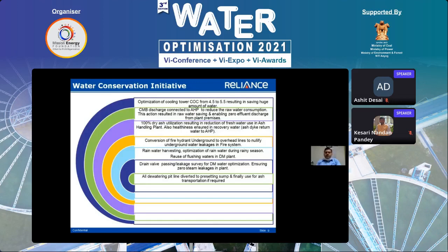Conversion of fire hydrant lines from underground to overhead. This was a major problem for us, because many of the fire lines were laid during the construction period from 2009 onwards, and many are buried below a 1.5 meter paved area, and frequent leakages occurred because of aging. So we took up a new project to improve our water consumption. Around 1 kilometer of line we have moved overhead, and we are planning 1.5 kilometers more in the BTG yard. This has resulted in major water savings.